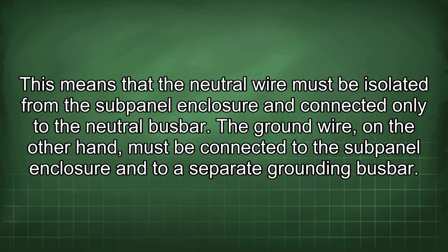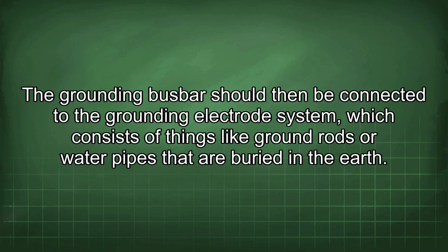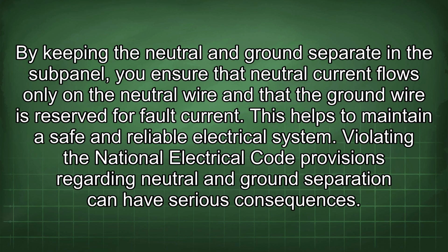The ground wire, on the other hand, must be connected to the subpanel enclosure and to a separate grounding busbar. The grounding busbar should then be connected to the grounding electrode system, which consists of things like ground rods or water pipes that are buried in the earth. By keeping the neutral and ground separate in the subpanel, you ensure that neutral current flows only on the neutral wire and that the ground wire is reserved for fault current. This helps to maintain a safe and reliable electrical system.